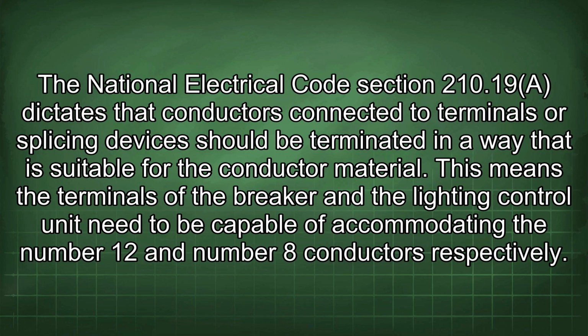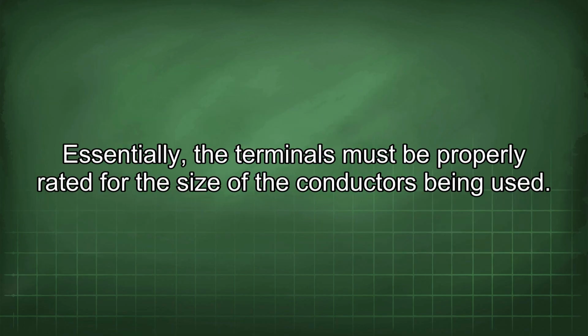The National Electrical Code Section 210.19 dictates that conductors connected to terminals or splicing devices should be terminated in a way that is suitable for the conductor material. This means the terminals of the breaker and the lighting control unit need to be capable of accommodating the number 12 and number 8 conductors respectively. Essentially, the terminals must be properly rated for the size of the conductors being used.